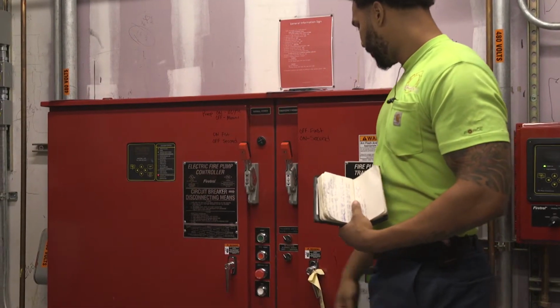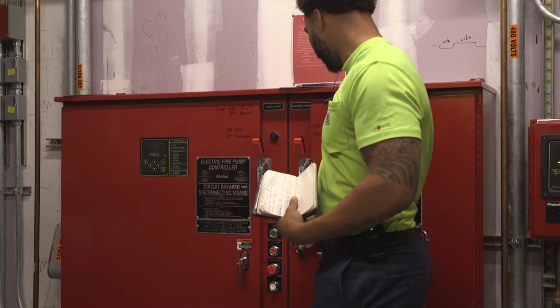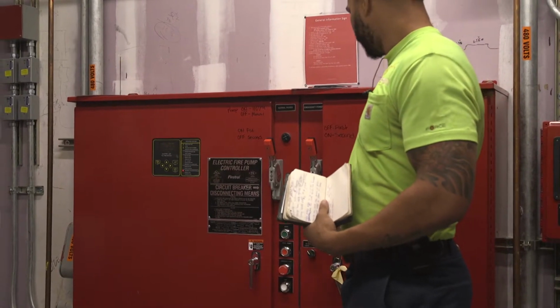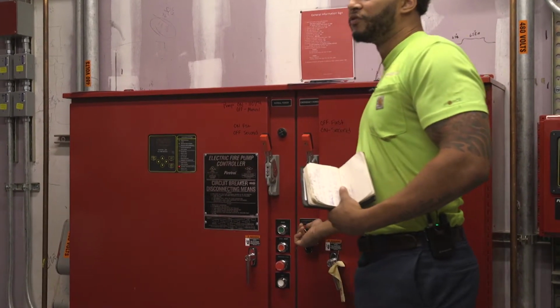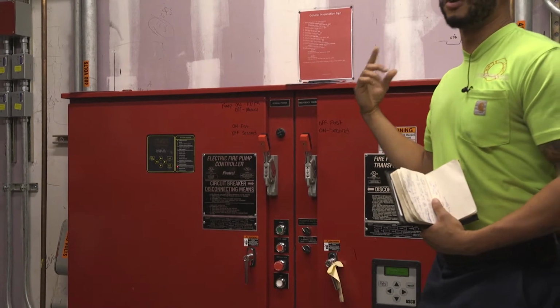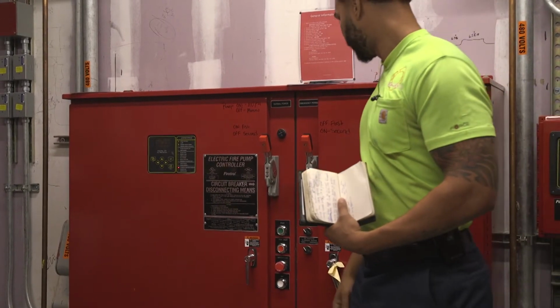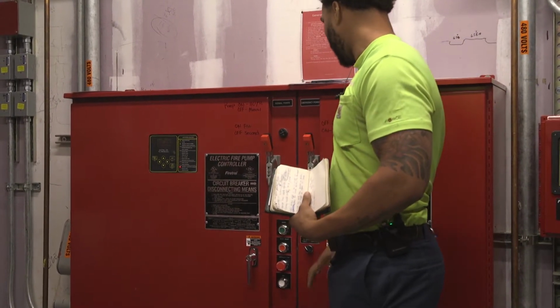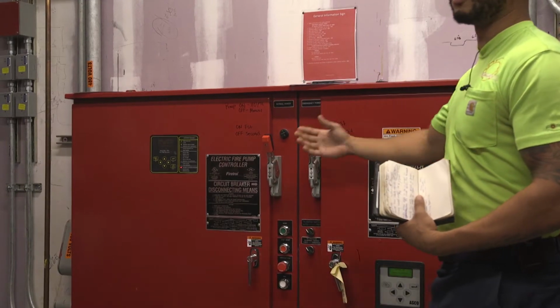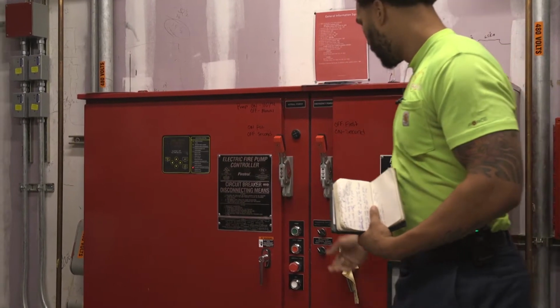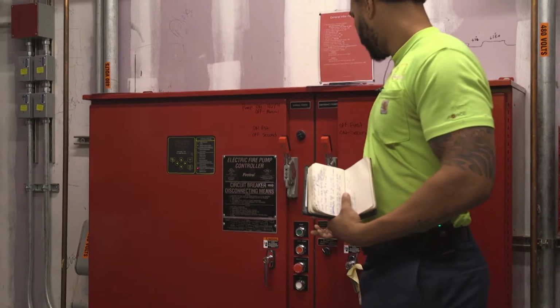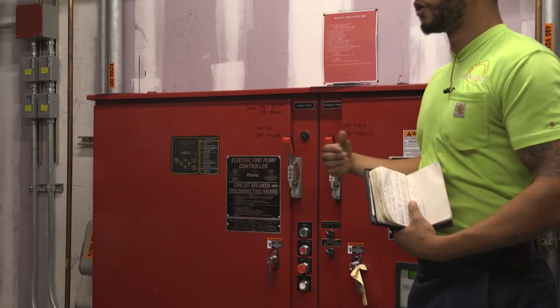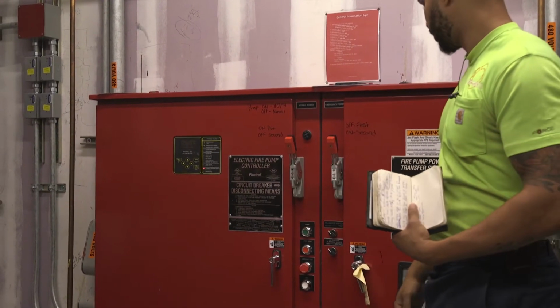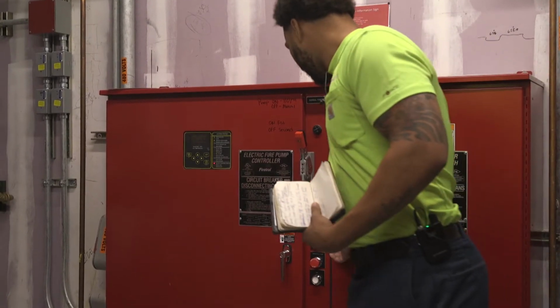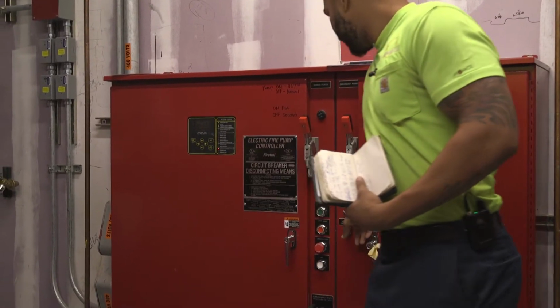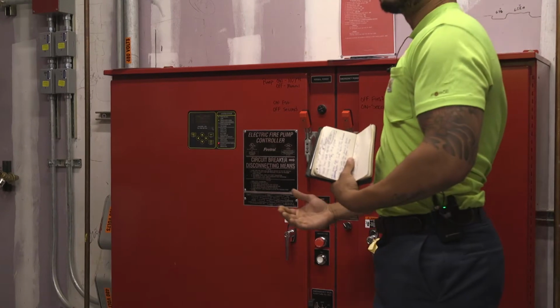We have 2 switches here. Our first switch is our transfer switch. Right now it's always going to be in the auto position. Our circuit breaker to the generator is always going to be in the on and auto position. If we had a loss of power, the controller is going to switch power automatically. If we hold the test button for about 10 seconds, it's going to automatically transfer to our generator power.